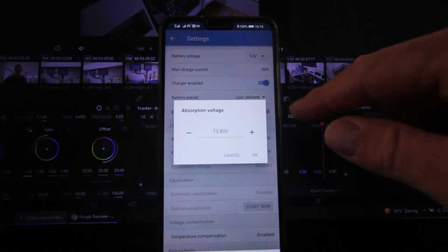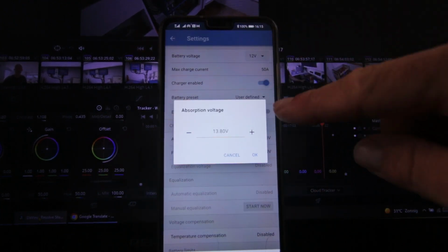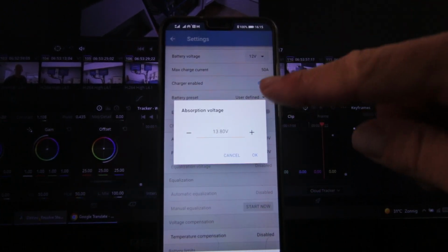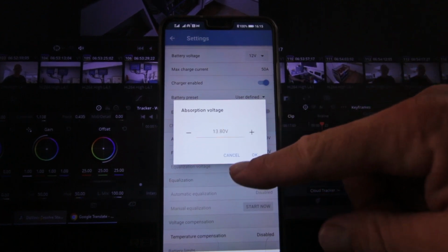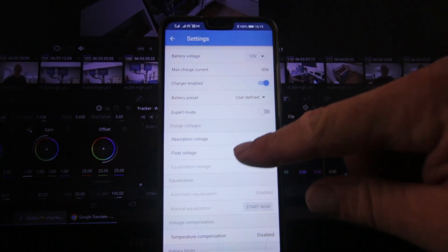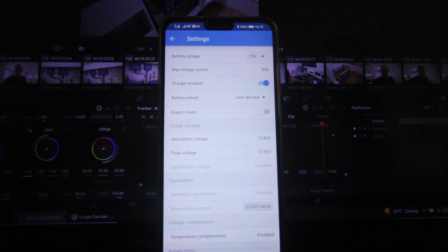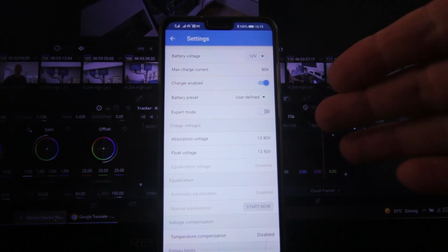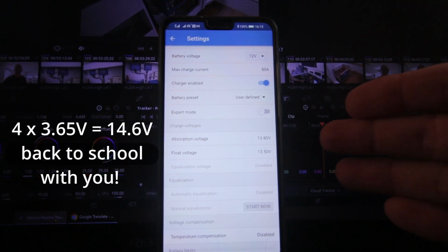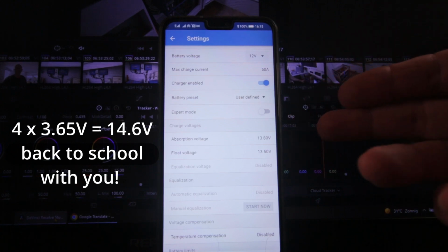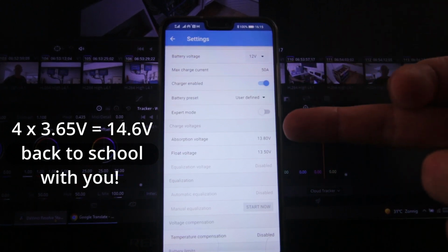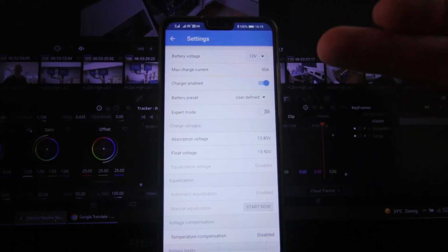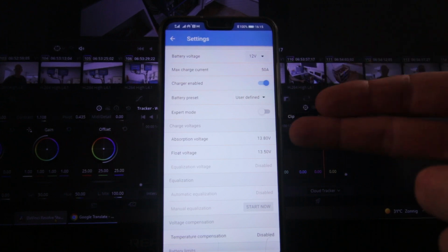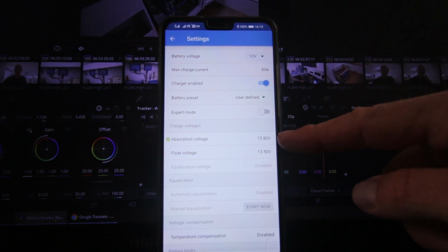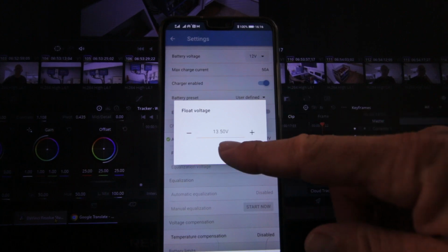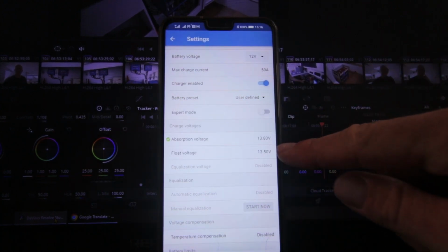Absorption voltage, that means the maximum voltage with which you're charging, and we've put it on 13.8. Of course, a lithium battery is maximum 14.4 I think, 4 times 3.65 being the maximum per cell. But lithium batteries don't like to be fully charged, so you leave some headroom. So float voltage 13.50, that's enough.